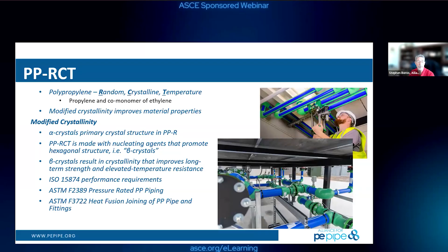So there are active standards for that. There's ISO standards—ISO 15874 is a very common one—but we also have ASTM standards domestically here in the US. F2389 covers all pressure-rated polypropylene piping, including PPRCT. And now there's a brand new standard out there on heat fusion joining of polypropylene, ASTM F3722. So there's a lot of things you can specify as an engineering community that's readily available. It's not proprietary—it's industry standard practice, which I believe brings a lot of benefits.